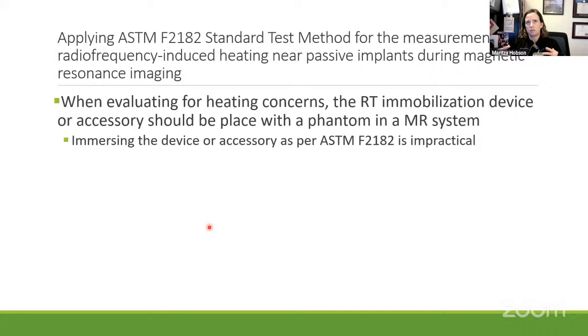So again, just as a reminder, these testing parameters are for implanted devices, so small devices. Obviously, we can't do that with external RT immobilization devices and accessories because it's just impractical. The bath would be too large, and after we take it out, we probably couldn't use the device because it'd be all sticky and who knows. So we recommend that external RT accessories and immobilization devices undergo RF heating tests that mimic the situation that they will be used in by using a phantom placed beside it.